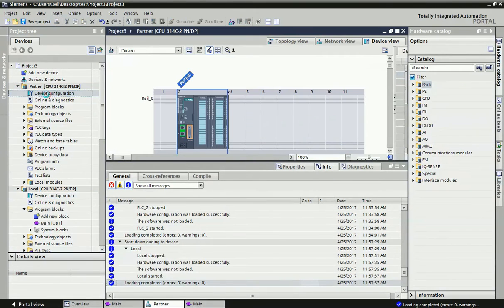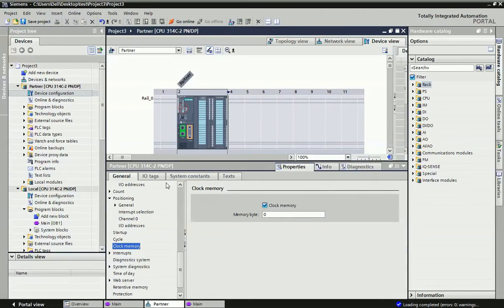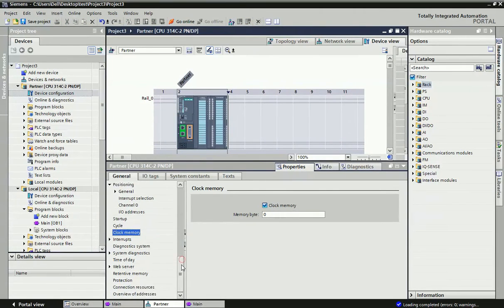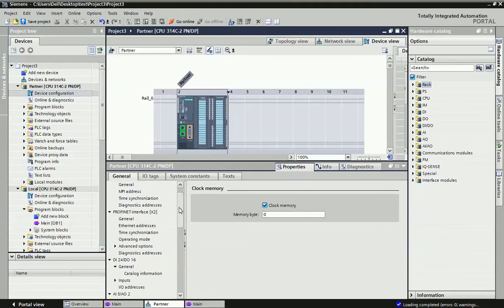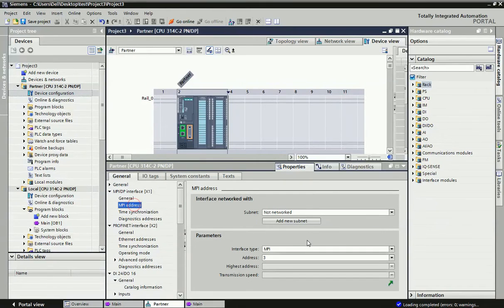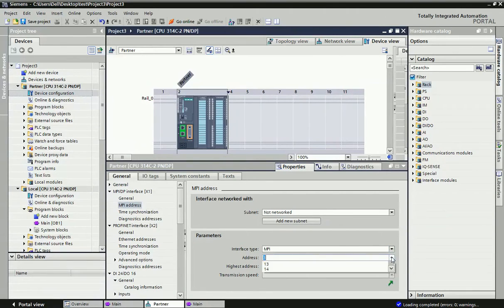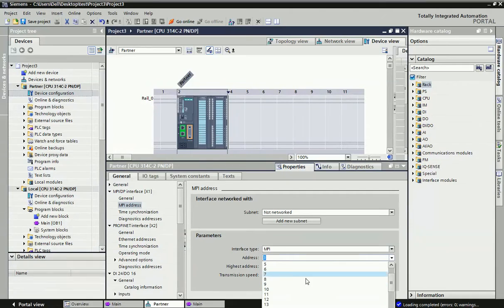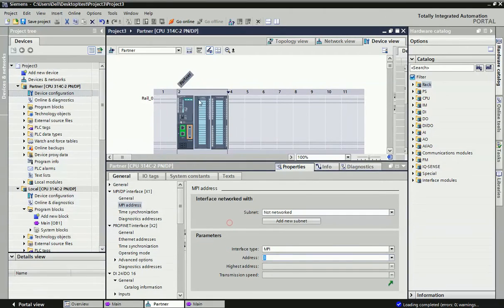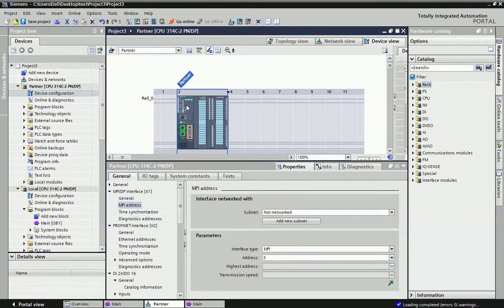The same configuration is done for the partner PLC — we enable clock memory and set the MPI address. For the local PLC we set address 2, and for the partner PLC we assign address 3. Up to 126 addresses can be assigned in this protocol.